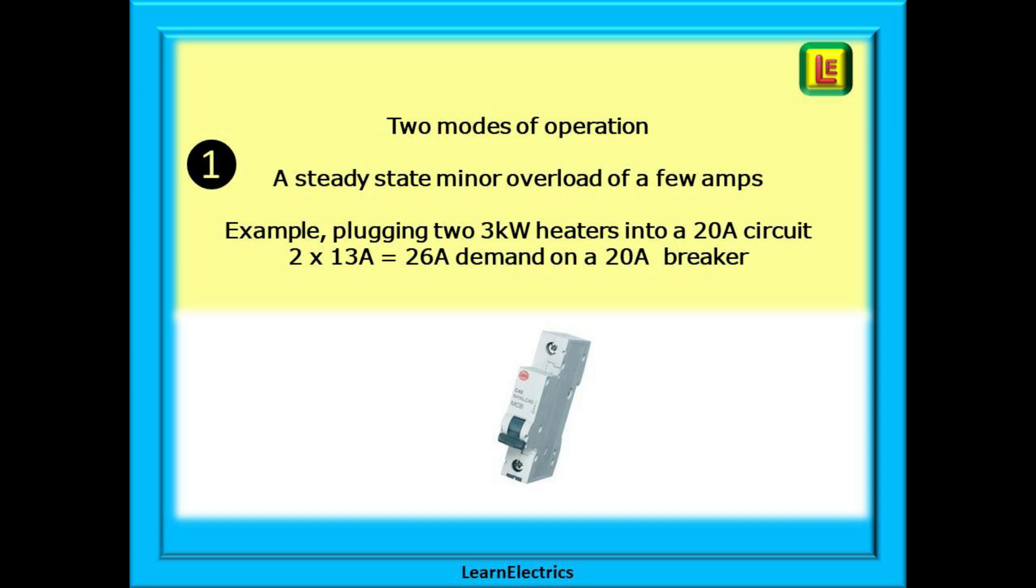A steady state small overload of a few amps will cause the MCB to trip after a period of time. For example, by plugging two 3kW heaters into a 20 amp circuit. This is two times 13 amps or 26 amps demand on a 20 amp breaker.